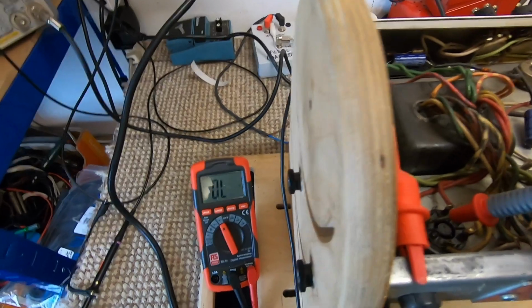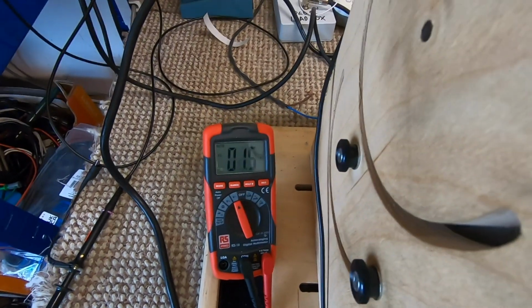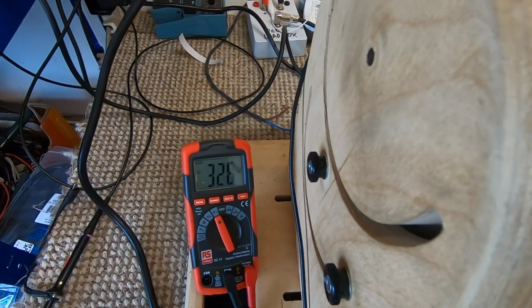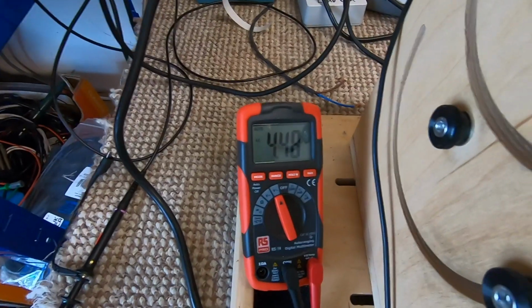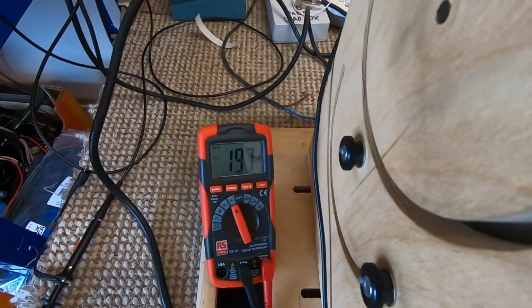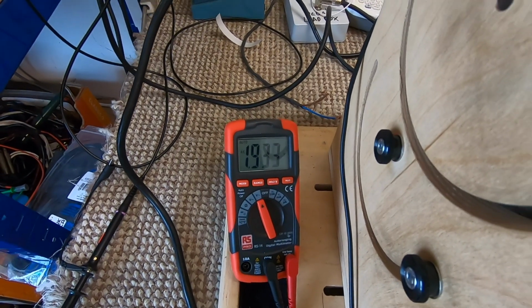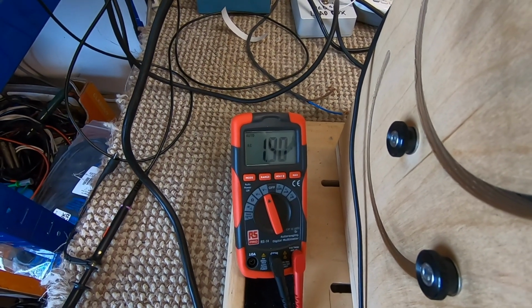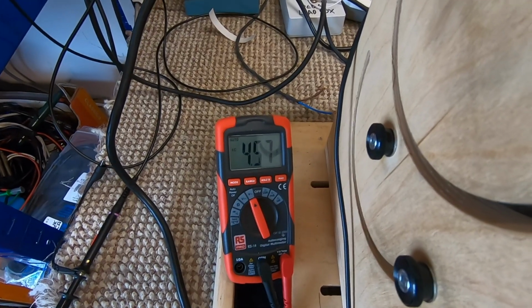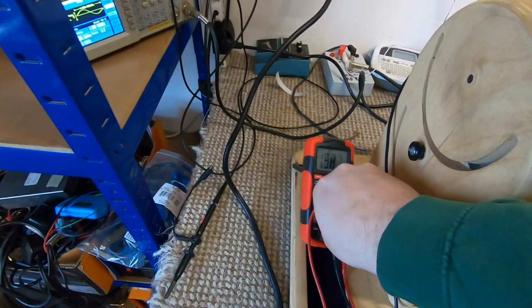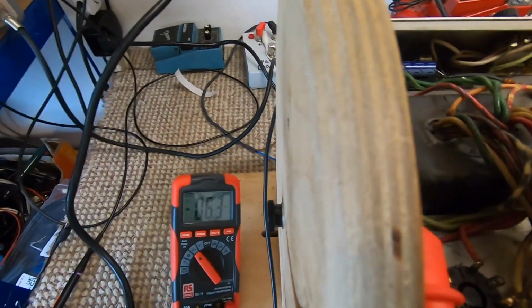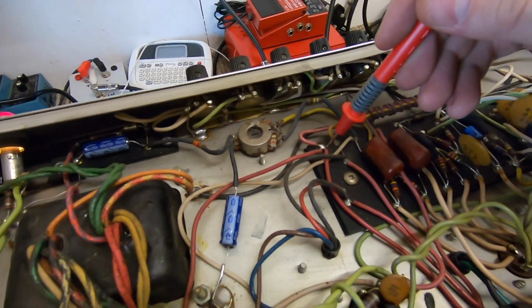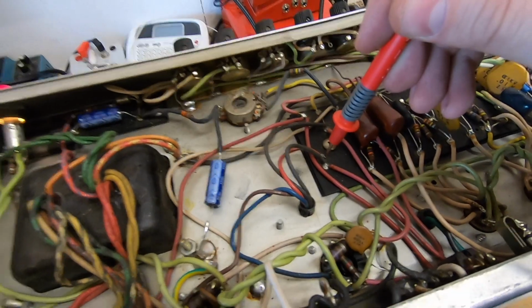Let's go to AC. Let's check our high voltage taps. High voltage on that pin, high voltage on that pin, got 5 volts on that pin, got voltage there, voltage there. We've got no DC volts coming off the rectifier. Nothing at all. If I measure throughout the amp in all the different places, it's nada, dead.